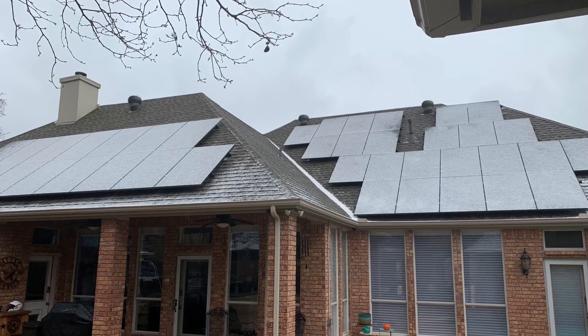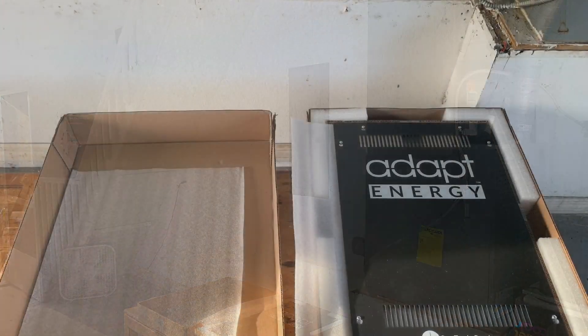You can literally set up an AdaptEnergy system within Crestron Home in a matter of minutes. Something we're working on right now is a state-of-charge load check. It seems like a simple concept, but the algorithms involved are pretty complex. Think about a home battery discharging and powering the home — the home recognizes that the battery's state of charge is below a threshold, and because of that, we turn off certain loads. But we need to choose the correct loads by priority and by current use, taking real-time information and applying conditional logic to define what happens automatically.